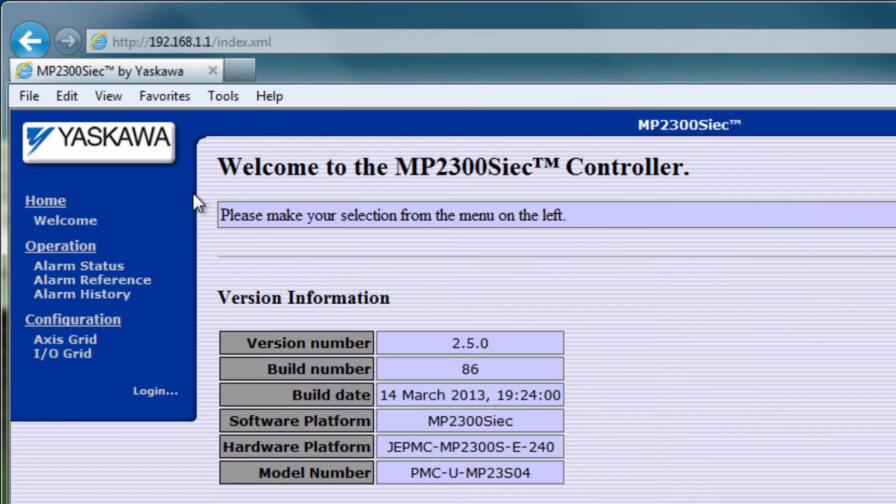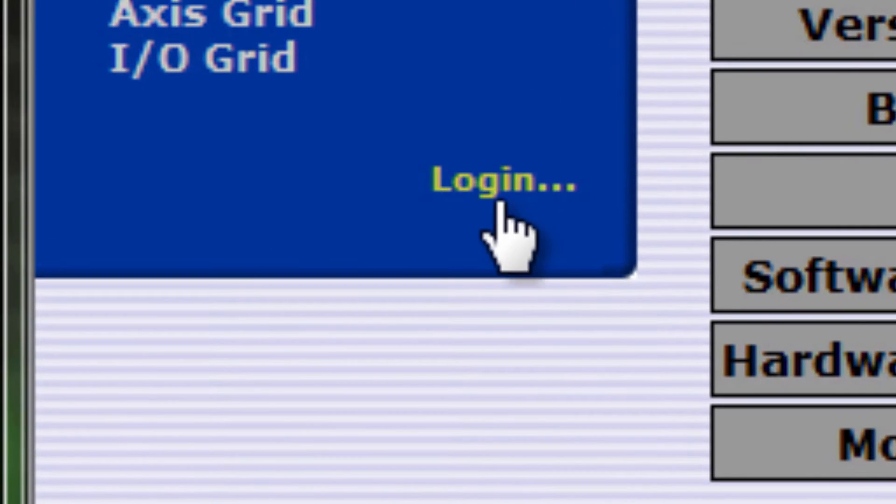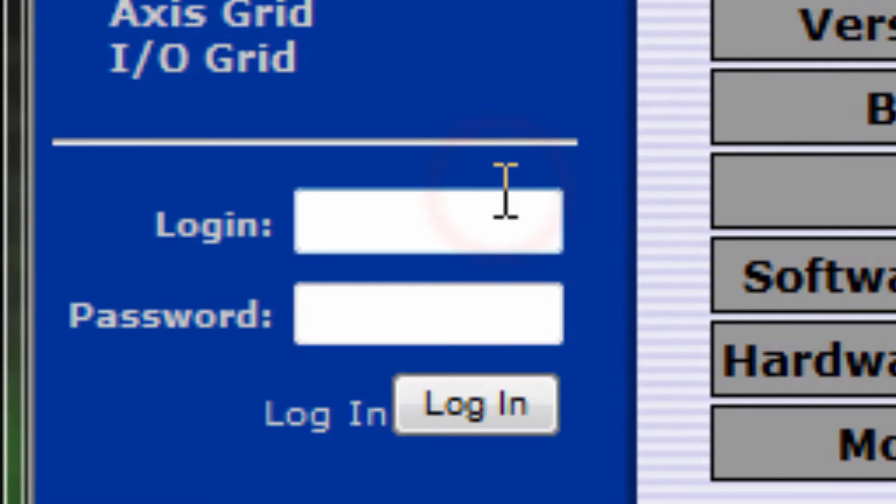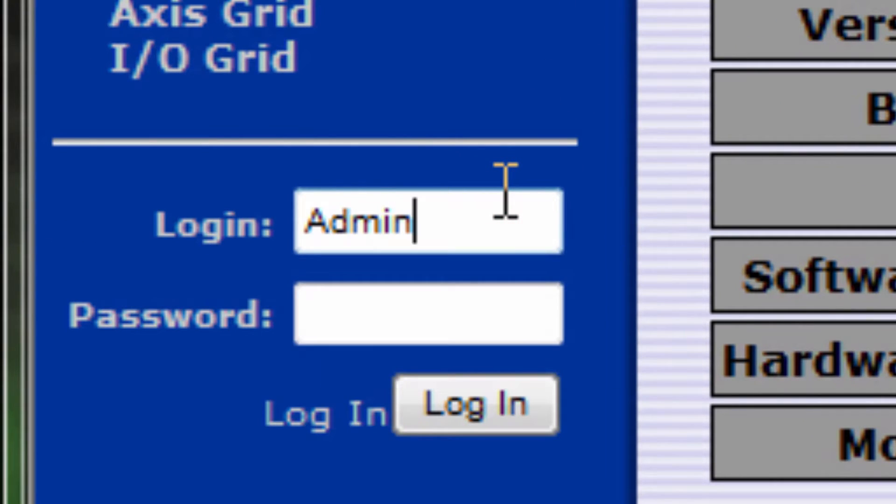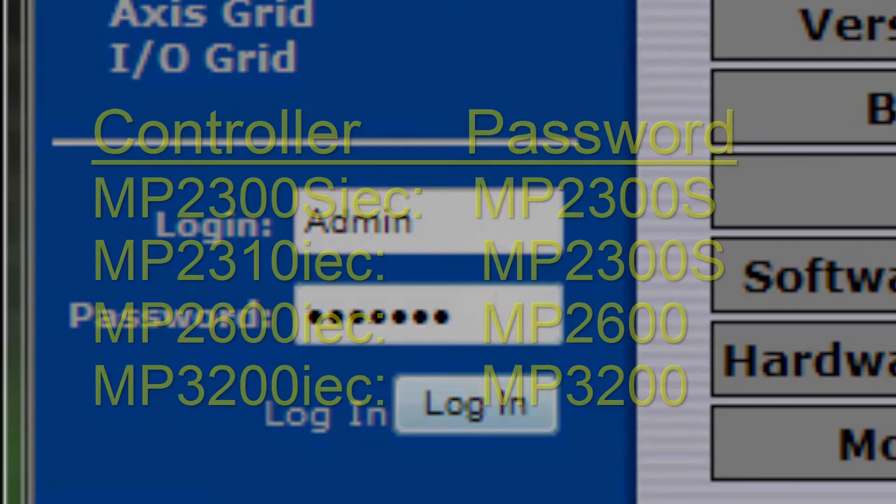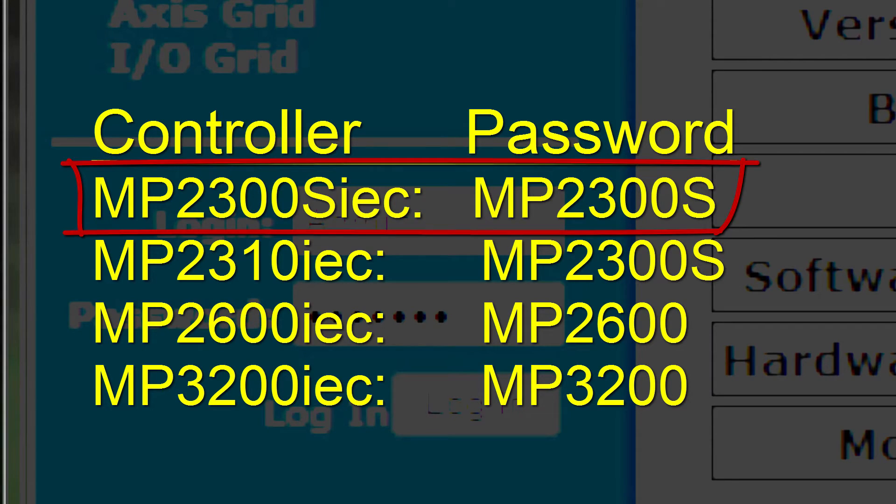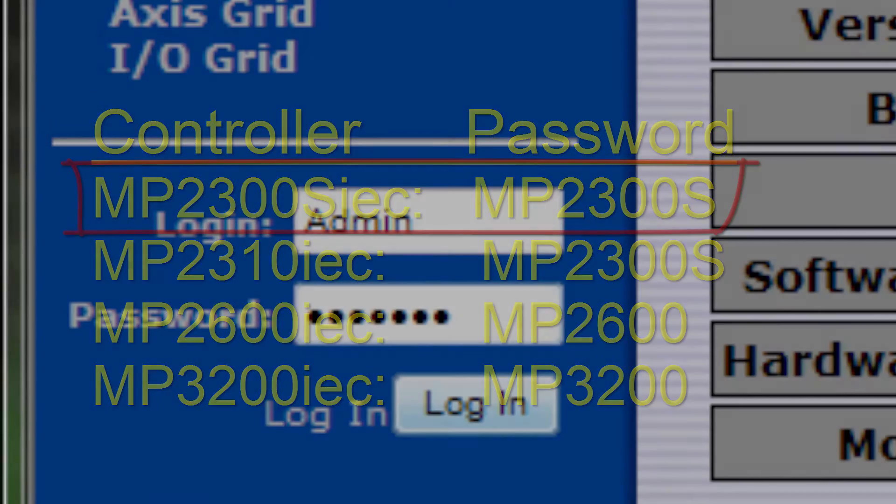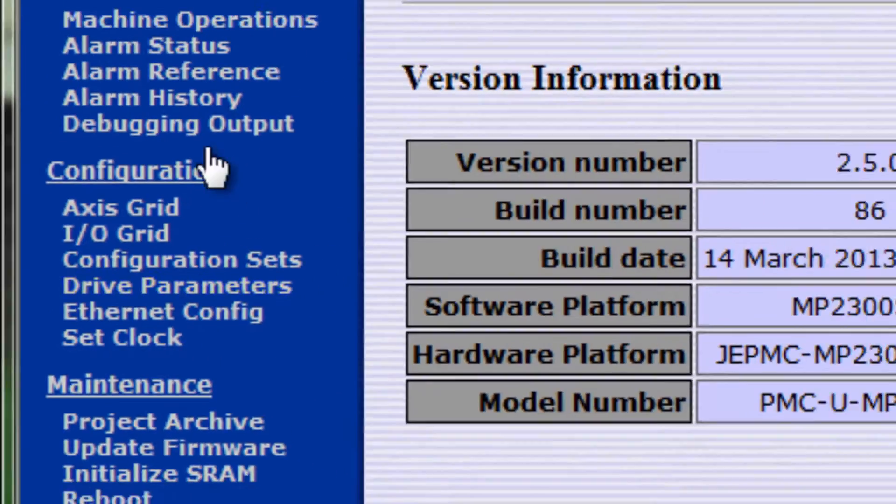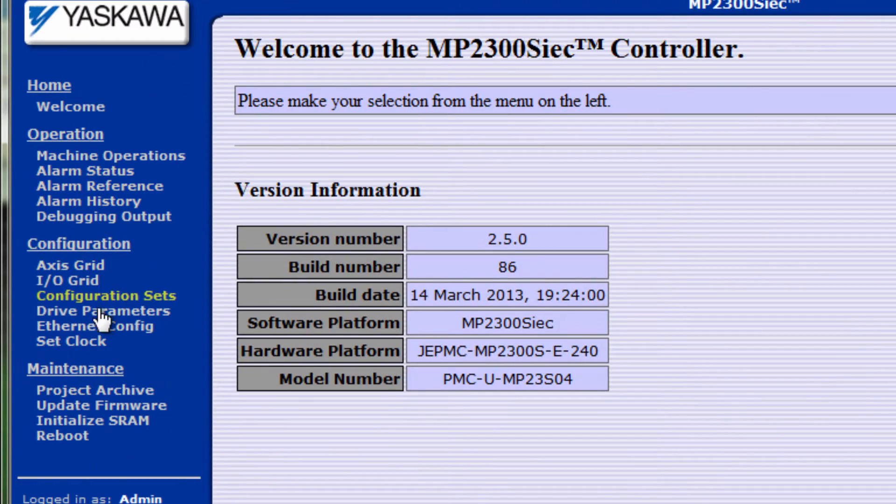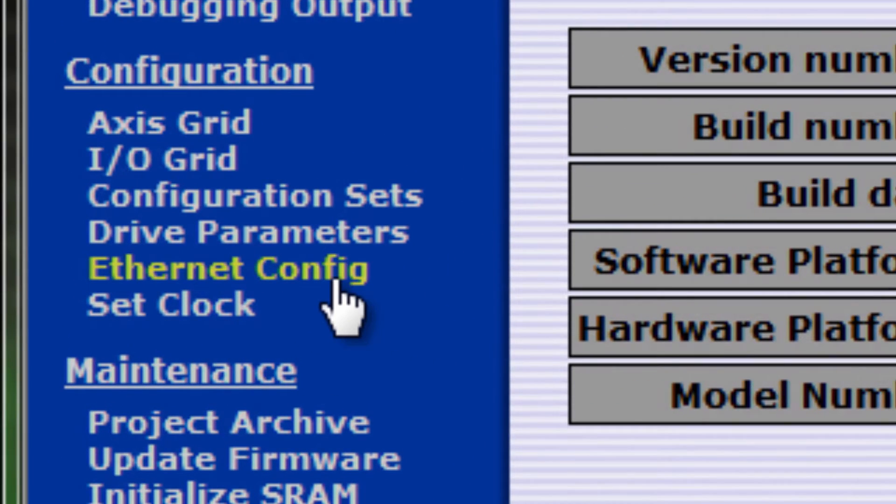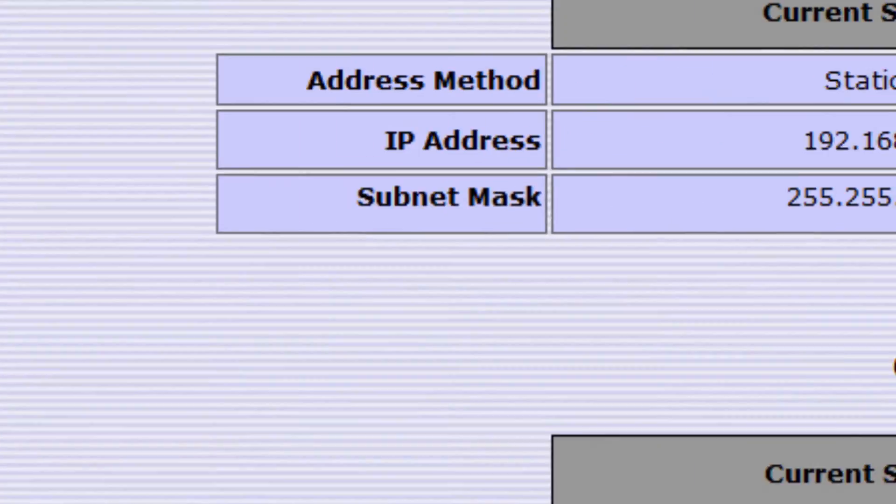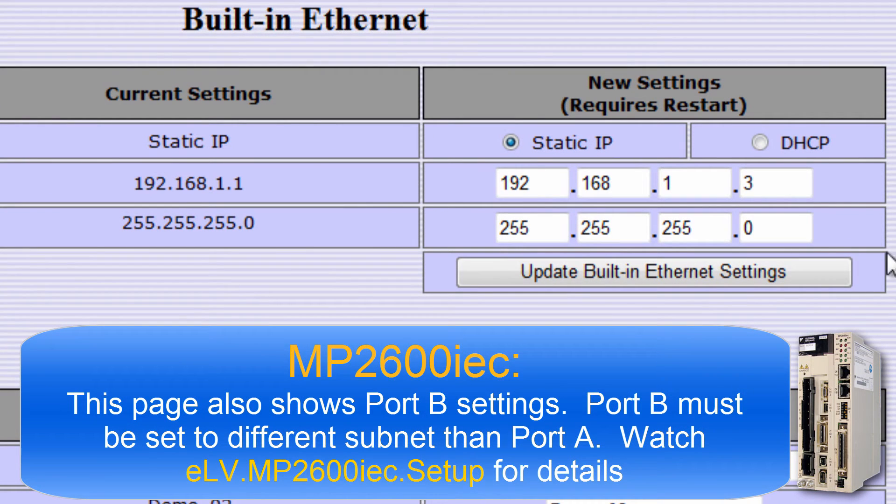To find the controller's configured address, log into the web server with username ADMIN with capital A and password MP2300S, all caps. Different MPIEC controllers have different default passwords. We're using the MP2300S IEC controller in this example. This opens links to all the available pages. Ethernet config shows the configured IP address 192.168.1.3.